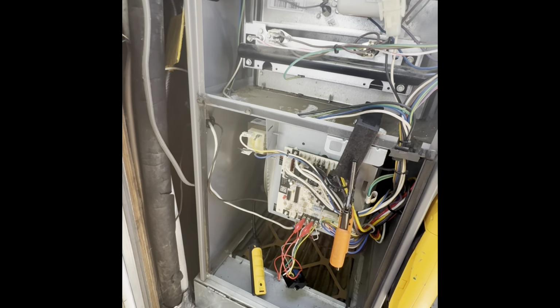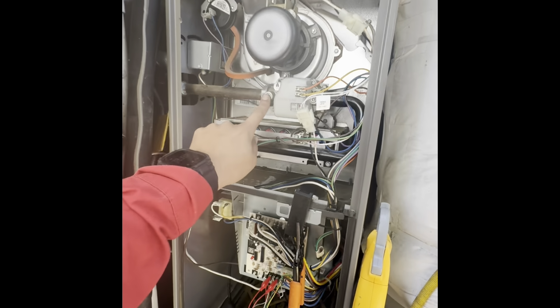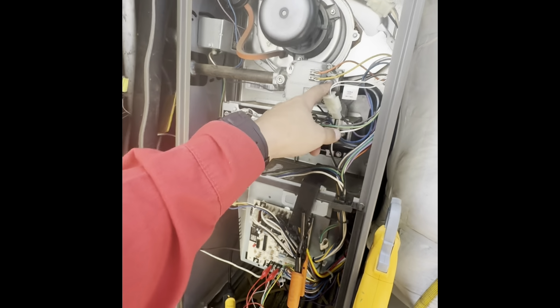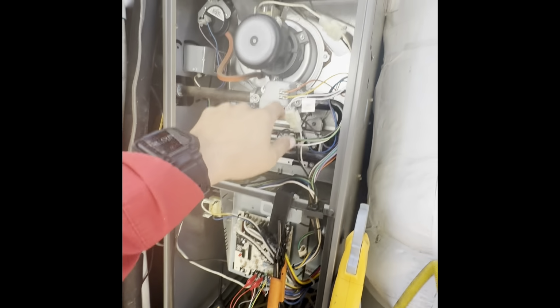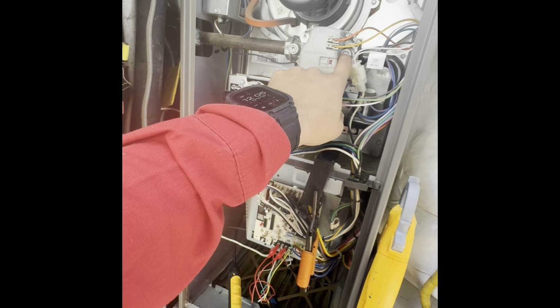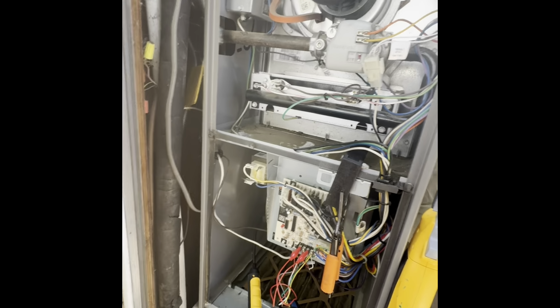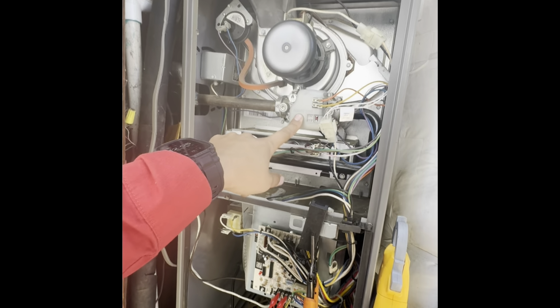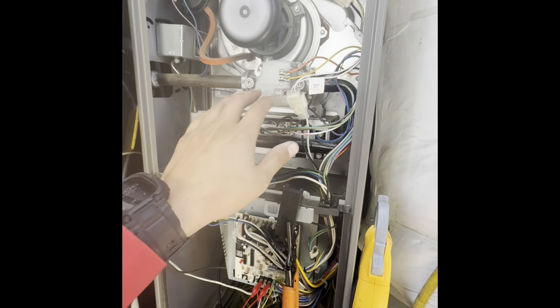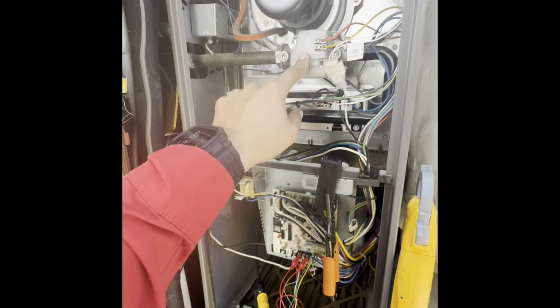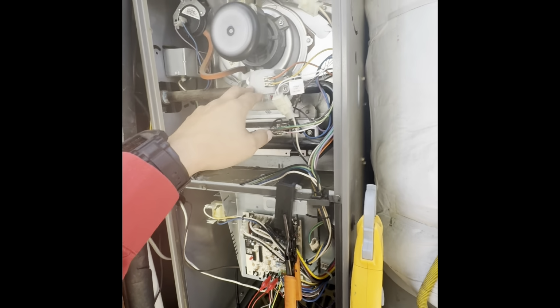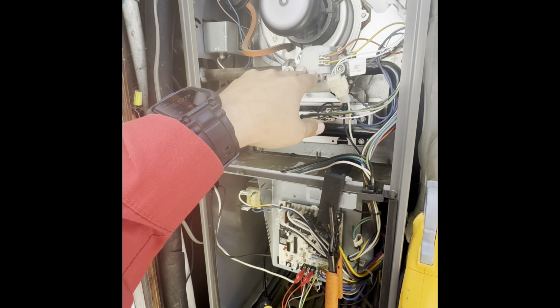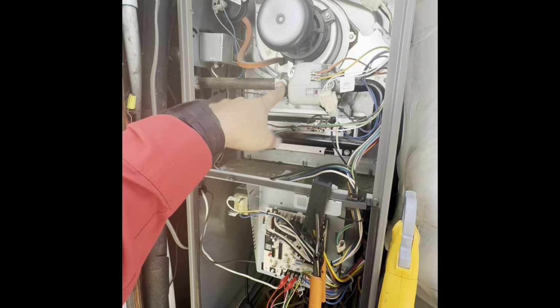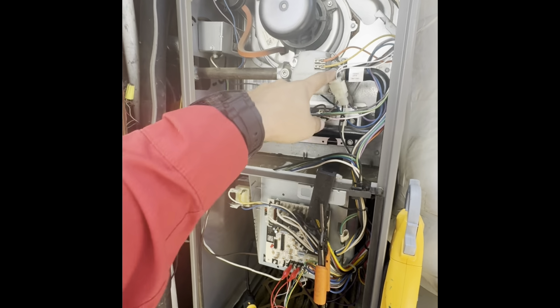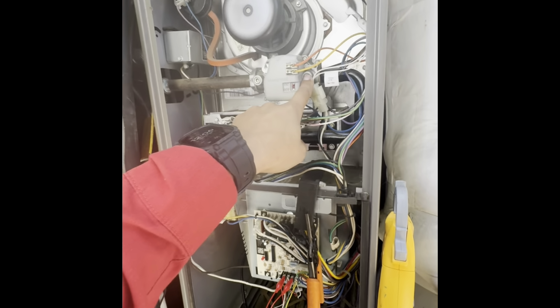So what I'm gonna do next is check the gas pressure. So remember, inlet, outlet, right? I'm gonna check the incoming gas pressure and the outgoing gas pressure to make sure it's operating within range. This is only a single stage gas valve, so I'm expecting to see somewhere between 3.4 and 3.5 at the outlet, due to the fact that it's natural gas. If it was propane and a single stage gas valve, we usually see around 10 inches of water column of pressure coming through the gas valve and about 13 at the inlet. This is natural gas. We're looking for 3.5, 3.4, somewhere around there.